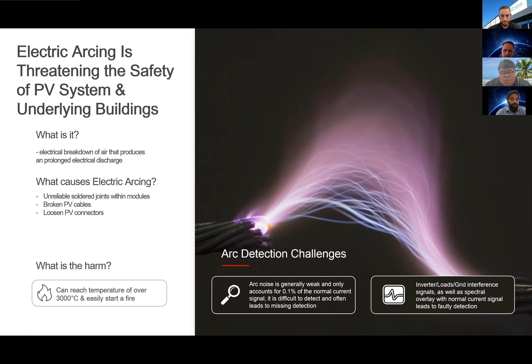If an inverter has to detect an arc, what are the challenges? So the arc will be detected as an AC overlay on the DC cable itself. And that arc can be deteriorated, attenuated, coming to the inverter because of a longer cable run. Or a bigger challenge to that is that any other electromagnetic interference on the roof or from any nearby electronic equipment might be read as an AC overlay on the DC, which will lead to a lot of false alarms, nuisance tripping. So that's why other inverter manufacturers who have this in their system, they disable it by default. They have AFCI disabled by default because of a lot of nuisance tripping.